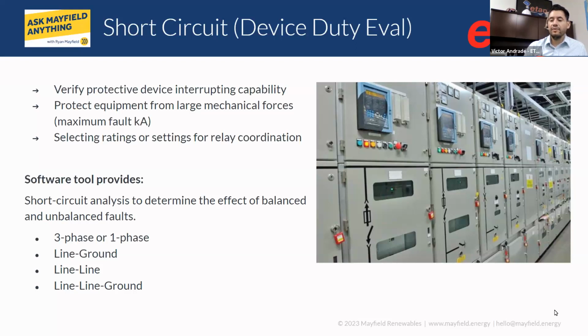And then just real quick to go over some of the sources of contribution, right? Because we talked about contribution from the grid. If you have any rotating machines, so synchronous generators, induction motors, synchronous motors, pumps, for example, those would add to the total contribution. Inverters will also have, right, even if they're smart inverters, if you look at the manufacturer provided data, there is some contribution that they provide as well. So all of these can be modeled in a simulation environment and design environment like ETAP, so that you can design the system safely, and you know exactly how much fault you can expect for a given location.